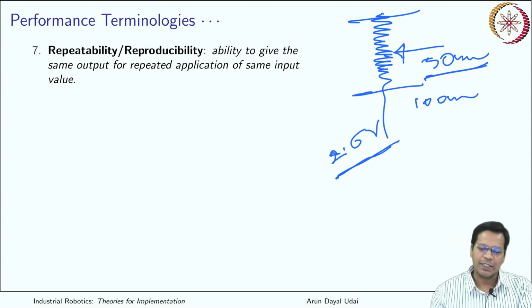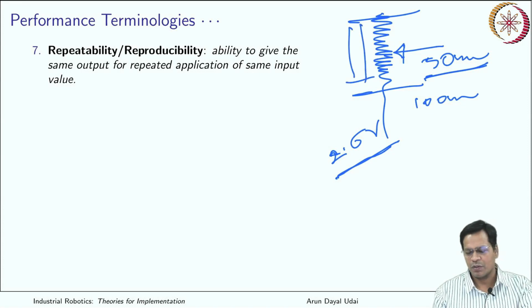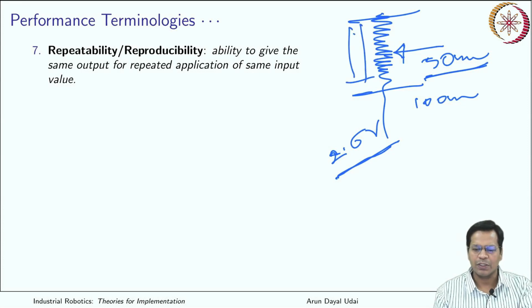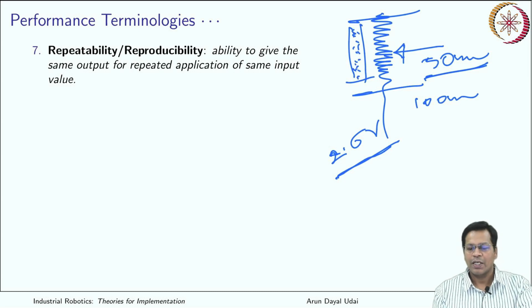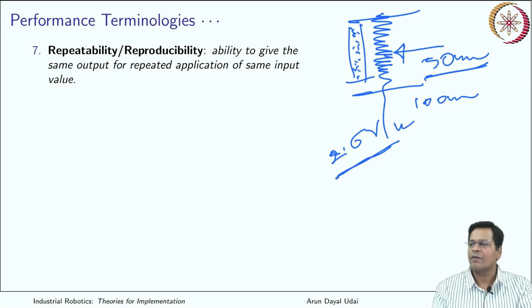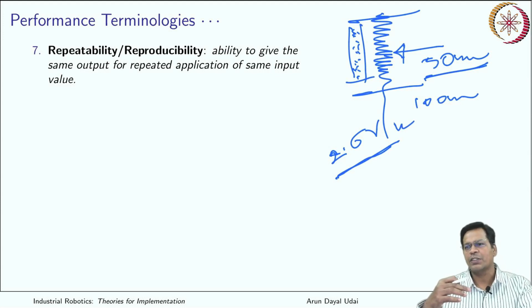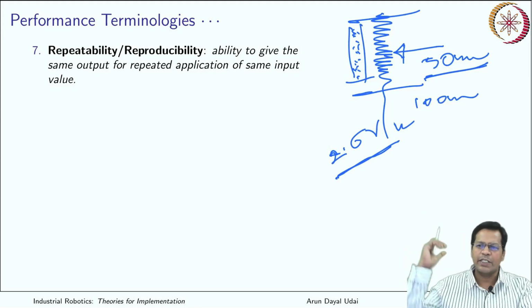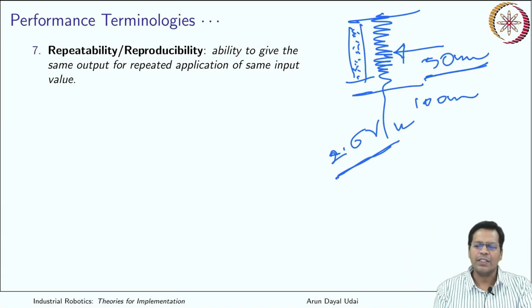But over time, this particular slider gets worn off. It goes bad due to dust on top of it, maybe moisture. In that case, this will not be the case anymore. So it is not repeatable if the value is accounted for over a period of time where things have gone bad. That definitely doesn't come under the purview of the repeatability definition.